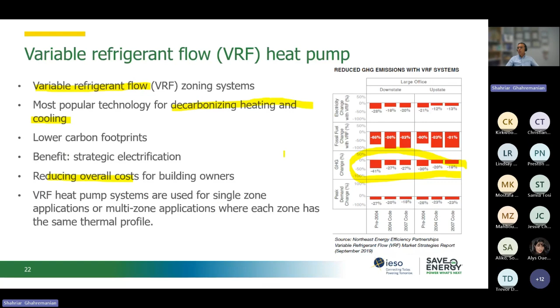We have two types of VRF heat pumps, I would say. Typically, we have the VRF heat pumps on the top pictures that you see here. So basically, we have an outdoor unit, and this outdoor unit provides heating to zone 2 and zone 3, for example. And then another outdoor unit, number 1, provides cooling. So unit 2 and unit 3, which are connected to one single outdoor unit, have to follow each other. So they cannot, for example, have unit 2 say that I want to run heating, and unit 3 say that I want to run cooling. That is not possible actually.